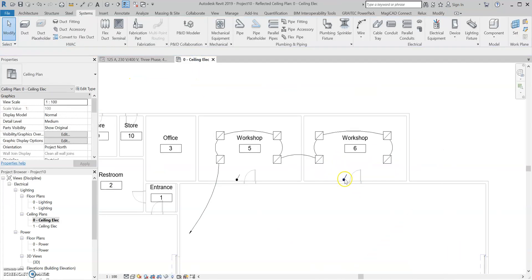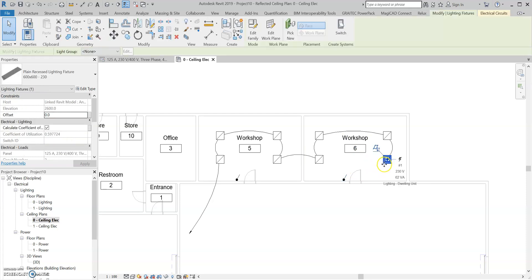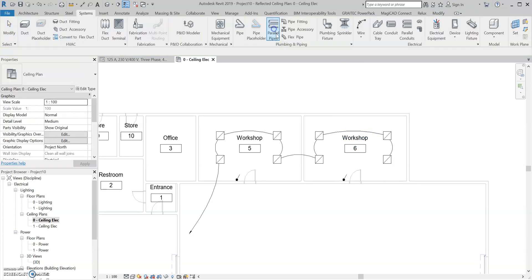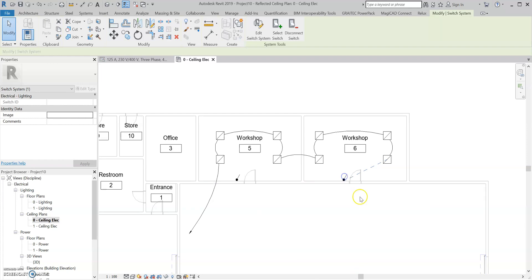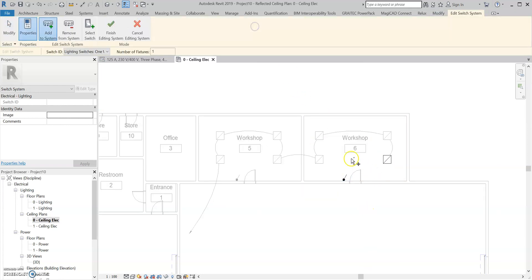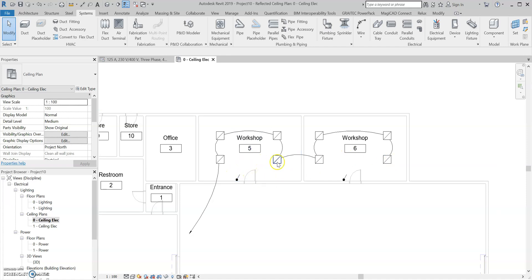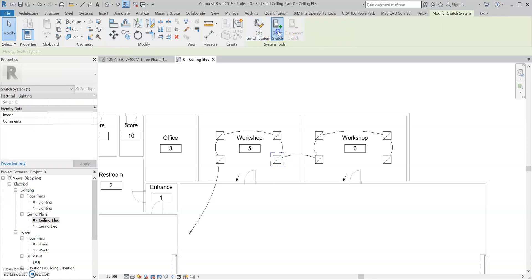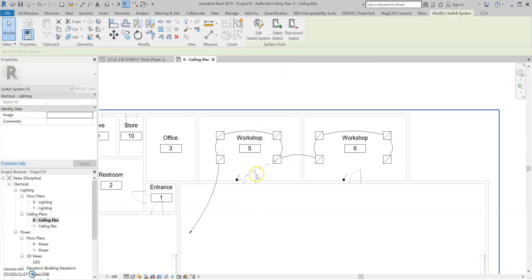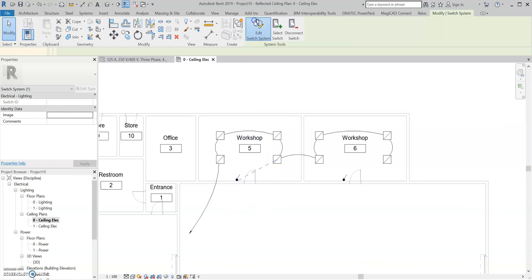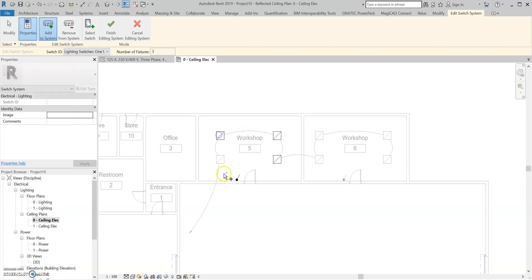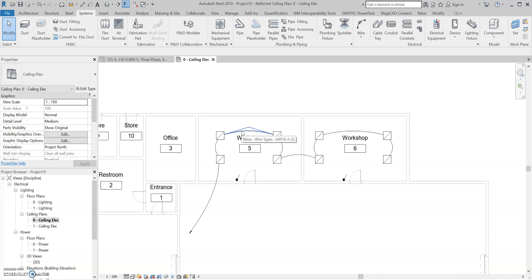Now I want to look at doing the switching circuit. I'm going to select the light fitting again and select Switch, select Switch again and tag it. Now we can edit the switch system and add the other lights we want switching from this switch. I'm going to add just Workshop Six because I only want Workshop Six to be controlled by this switch. Then I'll finish that and go over to the other room, select that light fitting, select Switch, and select Switch again. Now we can edit the switch system and start adding in the other light fittings and then finish editing.